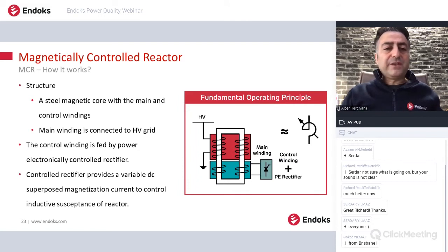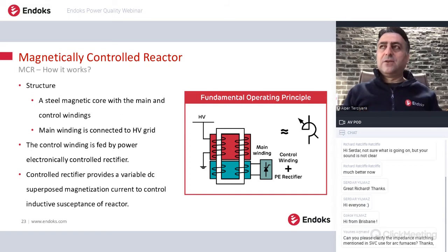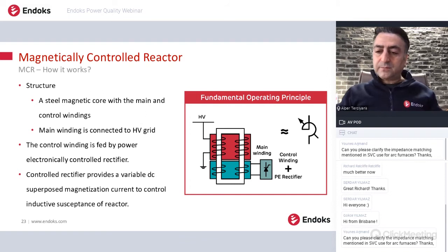And the magnetic control reactor is another type of SVC. Actually, it's a compact solution, because in this solution, there is a main winding and there is a control winding. And this control winding provides a DC superposed magnetization current into the core of the reactor. And so the reactor's susceptance or impedance is changing. So the reactive power is also being controlled.